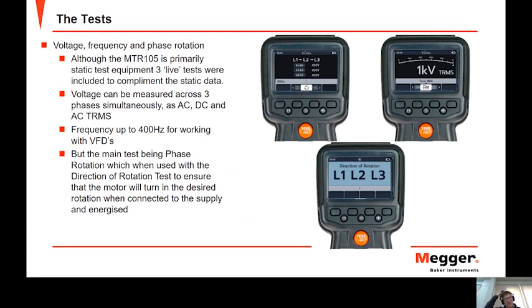So the voltage measurement feature is a little unusual for this type of handheld tester, but it provides a useful suite of tests. Voltage can be measured across 3 phases simultaneously. As you see in the upper left-hand image here, we've got 414 volts phase to phase, and we're also looking at the phase rotation and also the frequency.